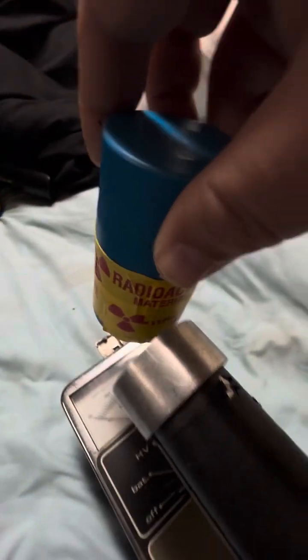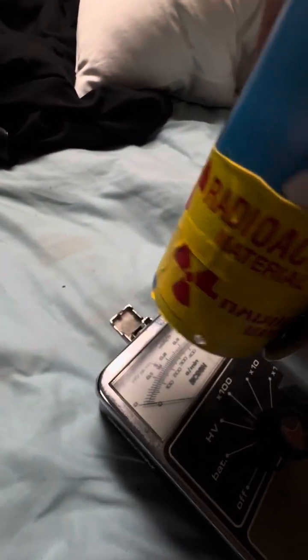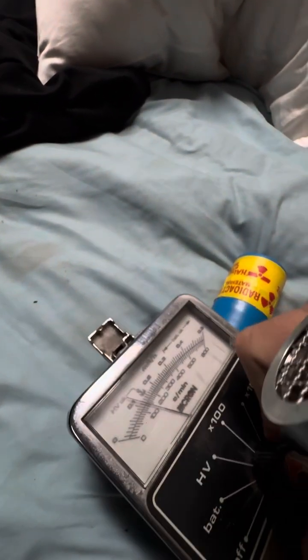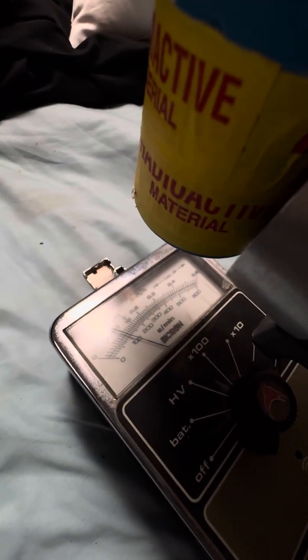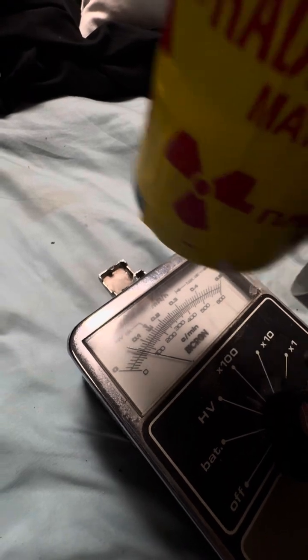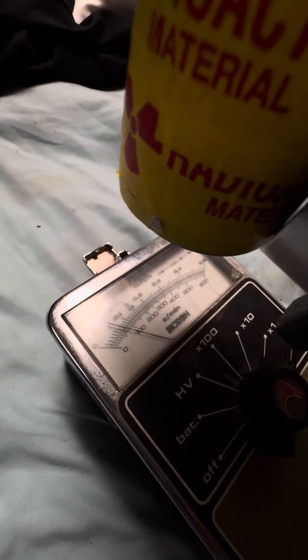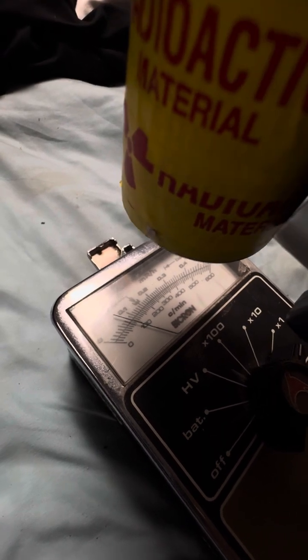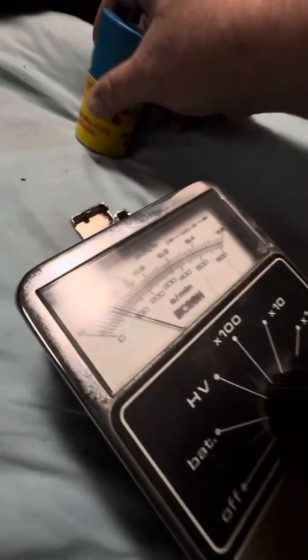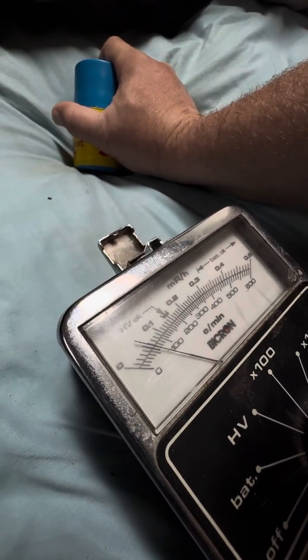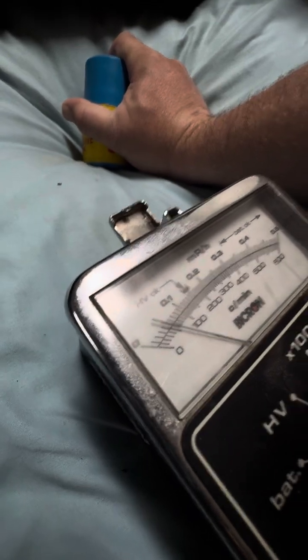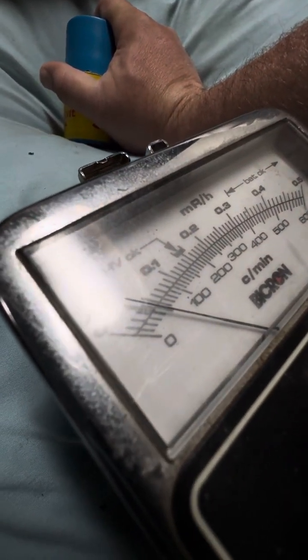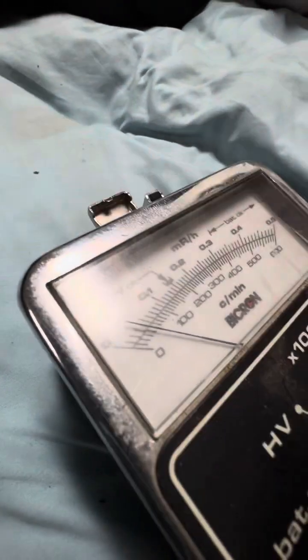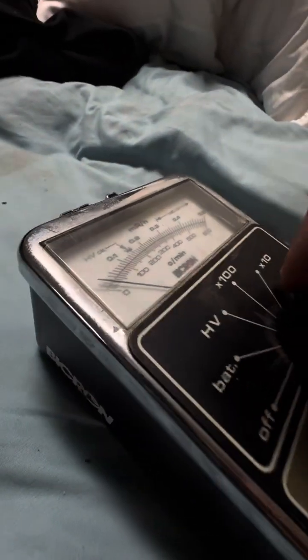It blocks almost all gamma radiation from this. Let's see if we can even detect it. Let's go down to the X1 scale. Yeah, inside the pig, as you can hear and see, the dose rate is very minimal, just barely above background. So the lead shielding does a very good job. And we're back to just background radiation. So as you can see, it does pick up background radiation. This particular probe usually counts about 50 or 60 counts per minute in my area.